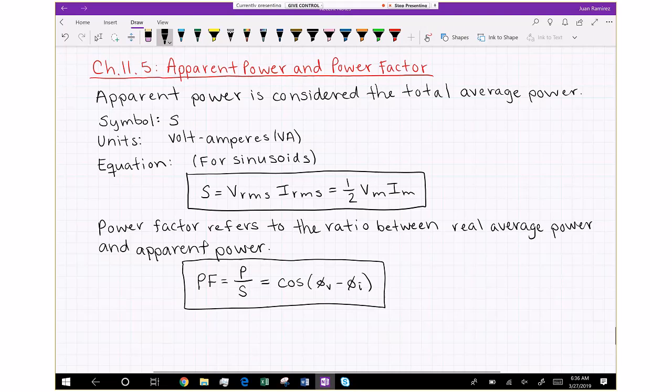We want to minimize that so other devices on the line are not going to malfunction. High power factors are typically desirable. We have standards for many electrical systems that have a minimum power factor requirement. Power supplies or higher power devices have standards like IEEE, IEC, UL. Each company will decide to comply to certain standards, which may require that a device doesn't draw power at a power factor less than say 0.95 or 0.9. When we design circuits, we often use something called power factor correction, which is trying to pull power that is resistive in nature so voltage and current are in phase.